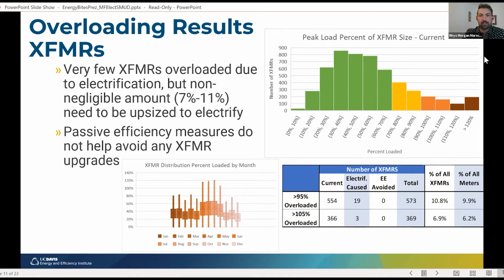That's good. Those transformers are in good shape. They're not overloaded. But there are about 10% that are in this 90% plus loading situation, which is not where you want to be. So it's a non-negligible amount that are already overloaded. When we add electrification, you'll see that there's a little bit of an impact, but ultimately only 20 or fewer transformers out of around 5,000 that are connected to multifamily buildings are overloaded due specifically to electrification.